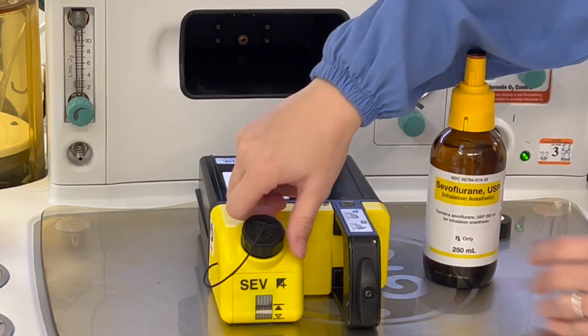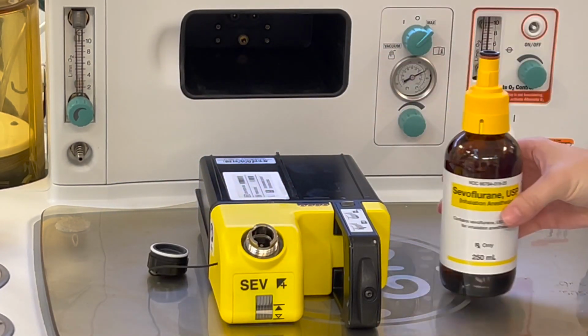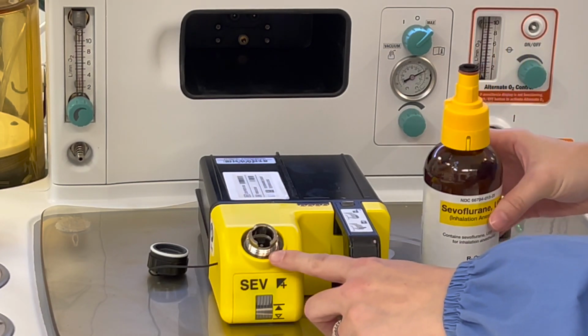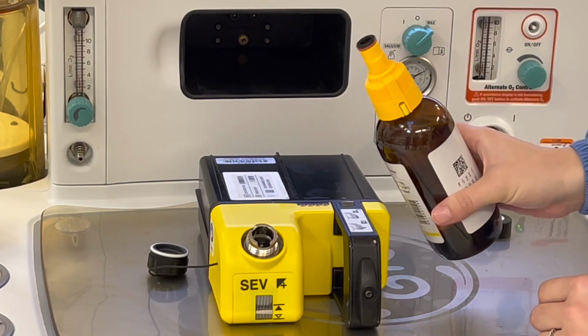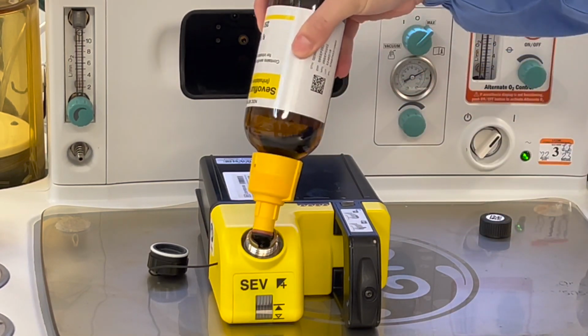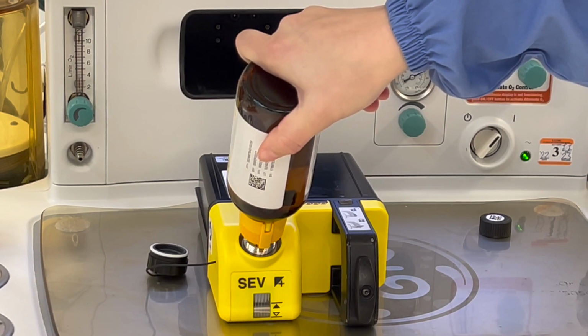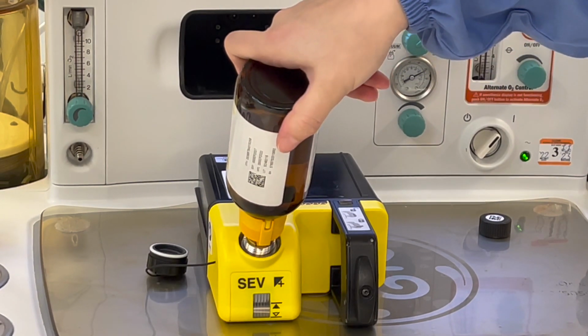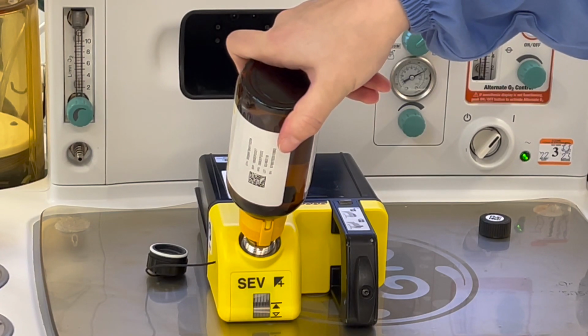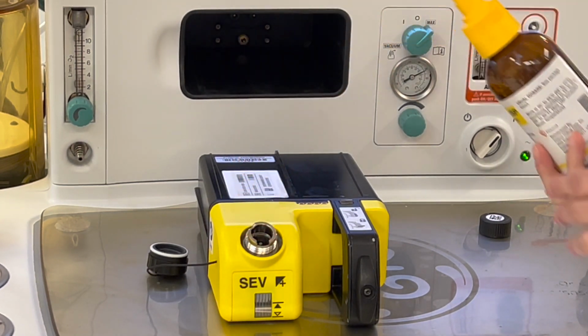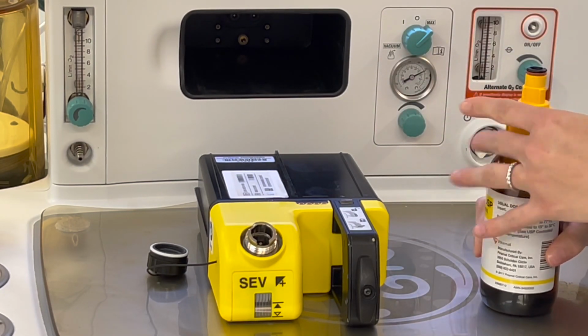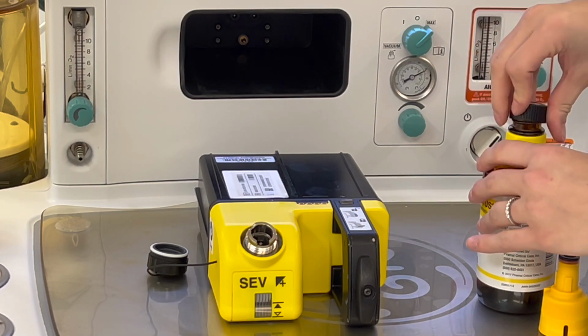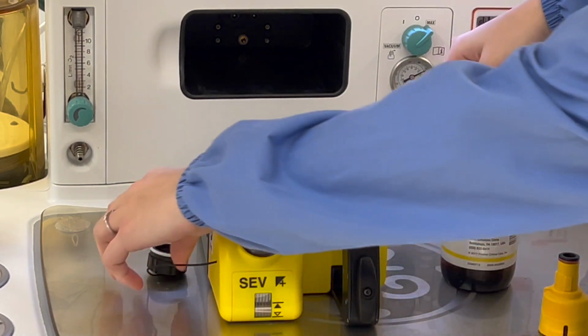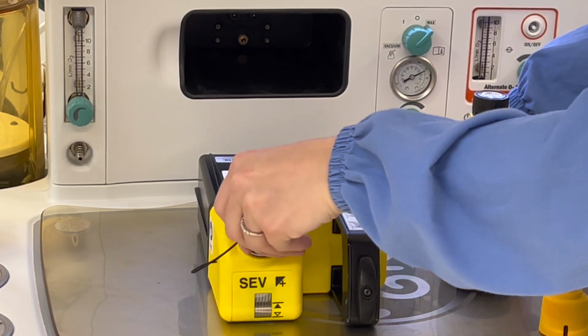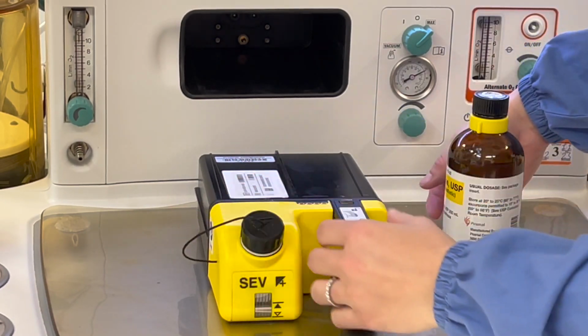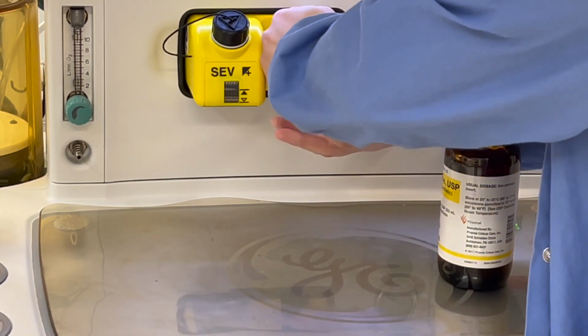Then you can take the bottle and you will open up the cap to the vaporizer, and the adapter will only fit this vaporizer. So you'll have to look for the grooves at the top of the adapter and make sure those match in order for it to fit. You can see you twist and then push and it should fall into place. So this vaporizer is already full, but normally you would see bubbling here, and then you would stop as the bubbling slows down and the black line reaches the top. Once it's full, remove the bottle and adapter, and then go ahead and place the original cap back on the bottle and then place the cap back onto the vaporizer. You have to make sure you do this correctly, because a loose cap on a vaporizer could be a source of leaks later down the line as you go to test your circuit.